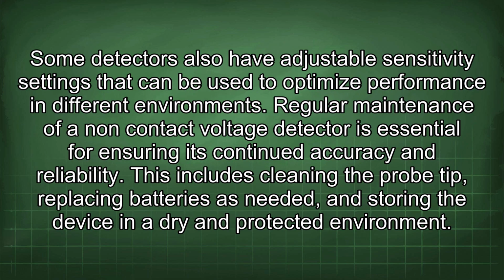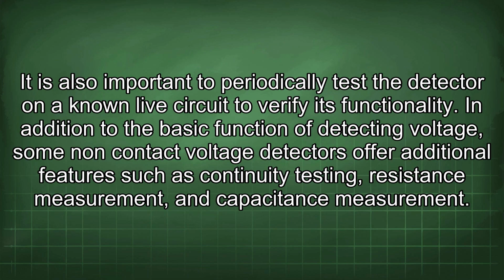Some detectors also have adjustable sensitivity settings that can be used to optimize performance in different environments. Regular maintenance of a non-contact voltage detector is essential for ensuring its continued accuracy and reliability. This includes cleaning the probe tip, replacing batteries as needed, and storing the device in a dry and protected environment. It is also important to periodically test the detector on a known live circuit to verify its functionality.